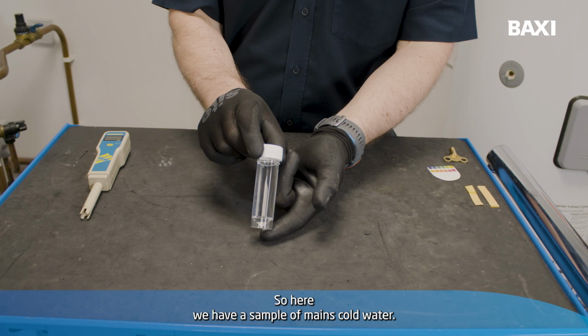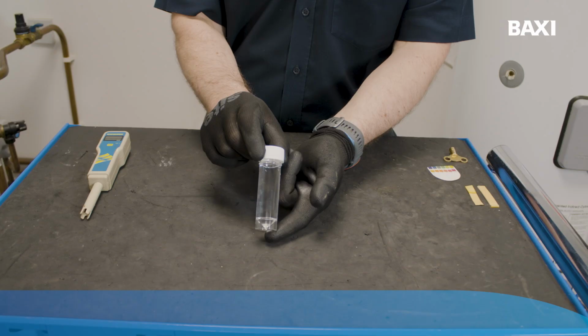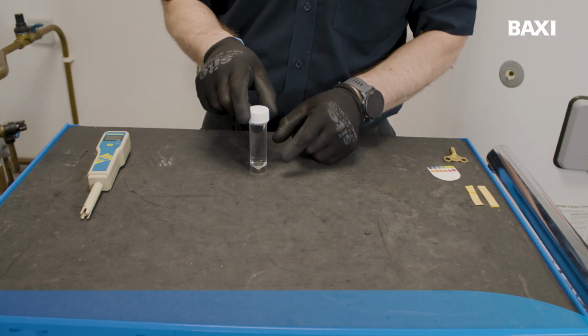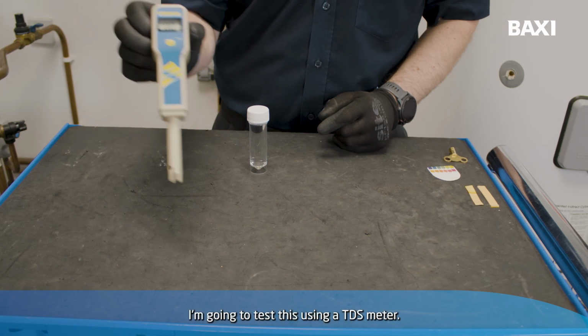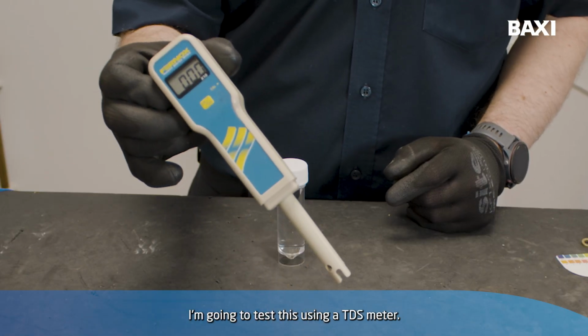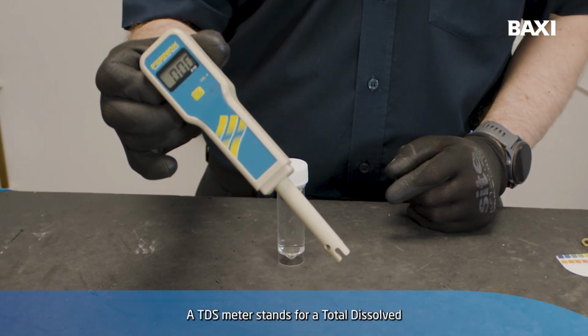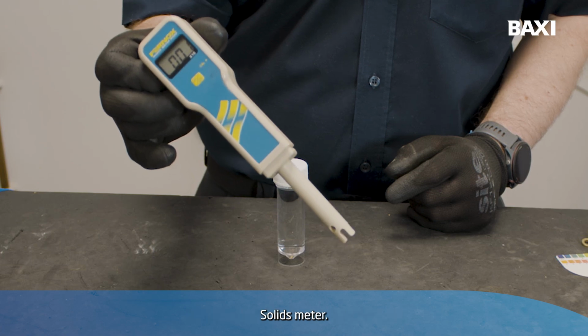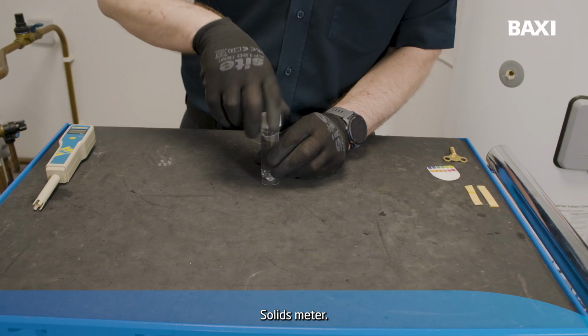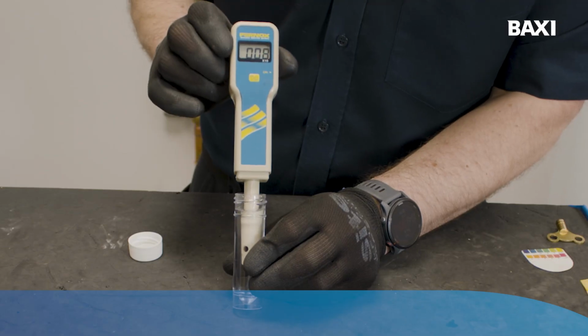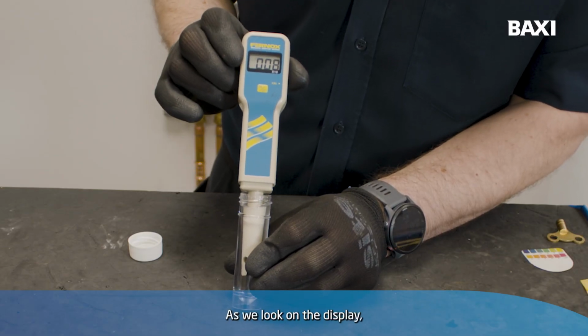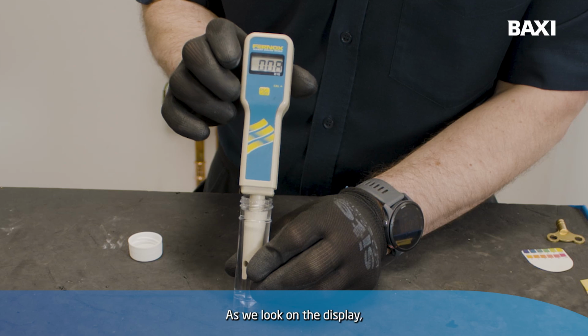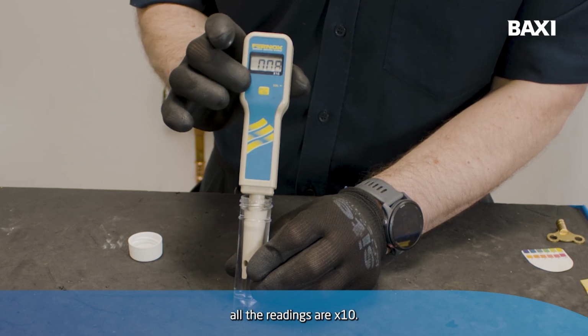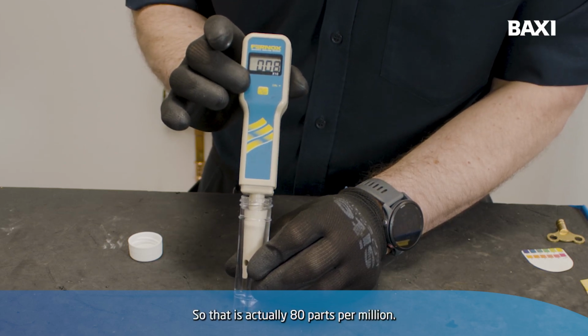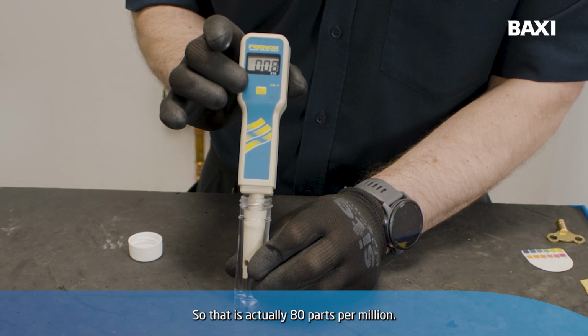So here we have a sample of mains cold water. I'm going to test this using a TDS meter. A TDS meter stands for a total dissolved solids meter. As we look on the display, all the readings are times 10. So that is actually 80 parts per million.